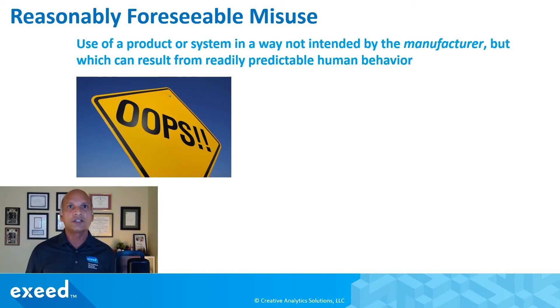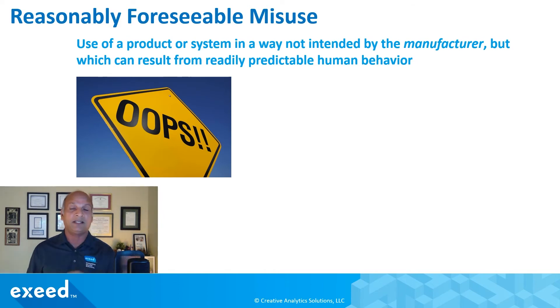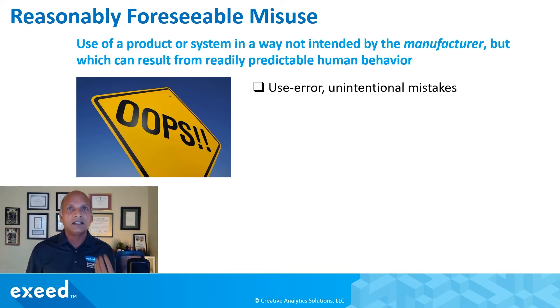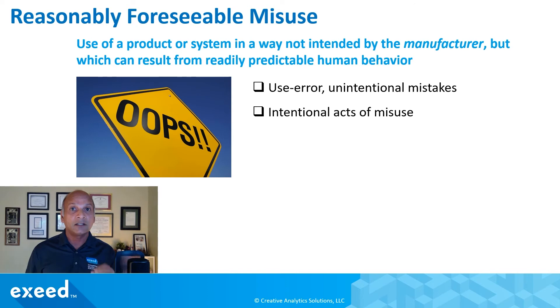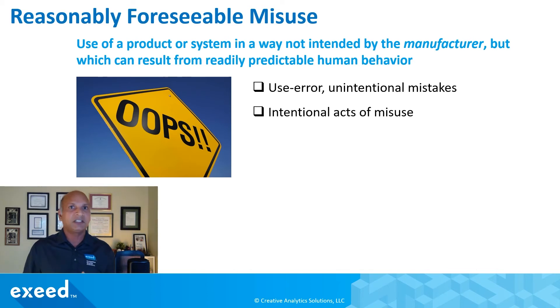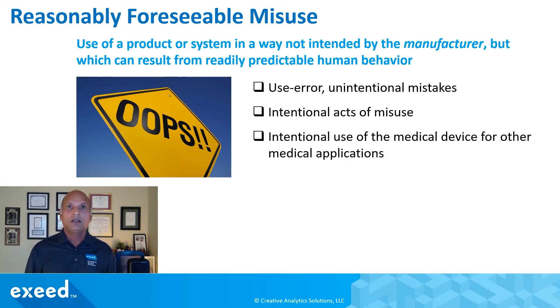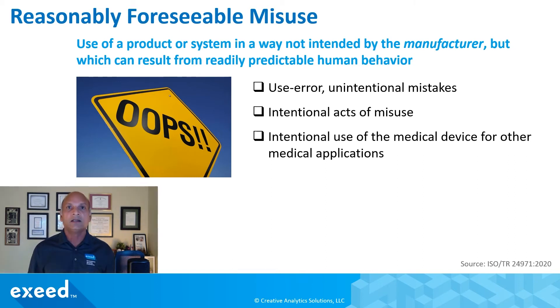What's a reasonably foreseeable misuse from an ISO point of view? It is use of a product or system in a way not intended by the manufacturer, but which can result from readily predictable human behavior. This includes use error — unintentional mistakes where people forget, get distracted, or misunderstand directions. It also includes intentional acts of misuse, such as ignoring instructions because someone thinks they already know how to use the device. Finally, there's intentional off-label use, where a doctor may decide to use your product for a different medical application based on their clinical judgment — which is perfectly fine, but something we need to anticipate.